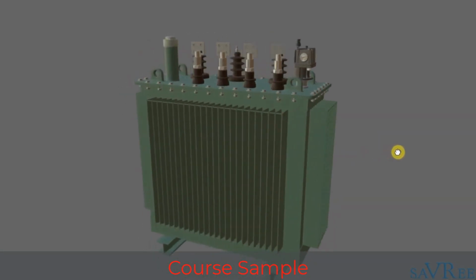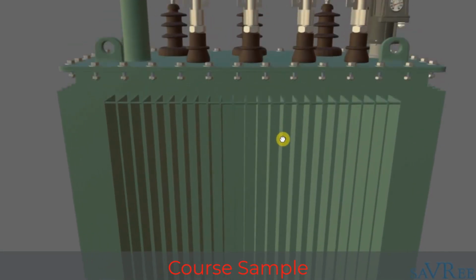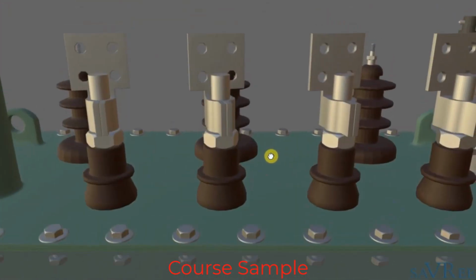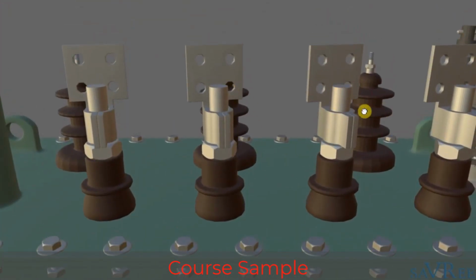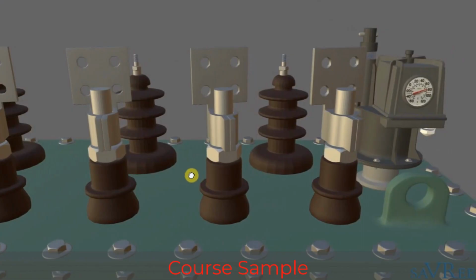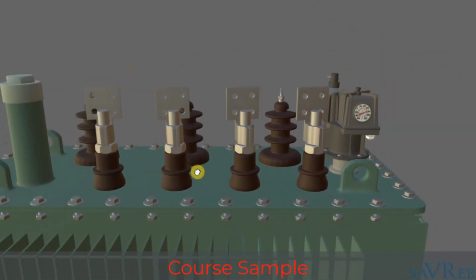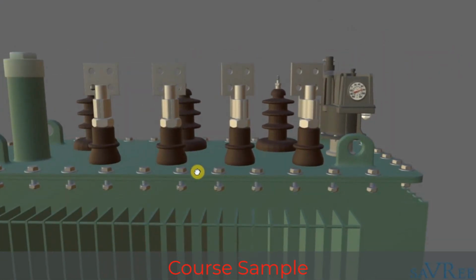We can see on the top that we've got some low voltage bushings - these four thick ones here. The reason they are the low voltage bushings, or the reason you can tell, is because the connections are very large. The reason they're large is because the voltage is low and the current is high.